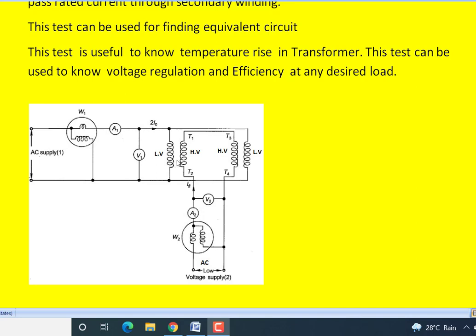And coming to the procedure, first we apply the rated voltage to the primary winding, keeping the secondary winding open, meaning these windings are not excited by the secondary side voltage source. Then if the voltmeter reading V2 is non-zero, showing some value, we interchange these connections. Instead of connecting T4 like this, we connect T4 here, so that T4 and T1 become in series, whereas T3 will go to the supply. In that case these windings automatically become in series opposition.